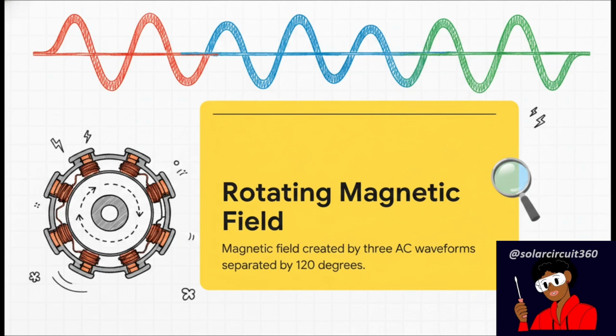It's beautiful, really. It relies on a rotating magnetic field. The three alternating current waveforms coming from your power source are separated by exactly 120 electrical degrees. So as these three distinct phases peak and fall in a very specific sequence, they create a magnetic field inside the motor stator that literally sweeps around in a perfect circle. And the rotor, right in the center, it just chases that rotating magnetic field.